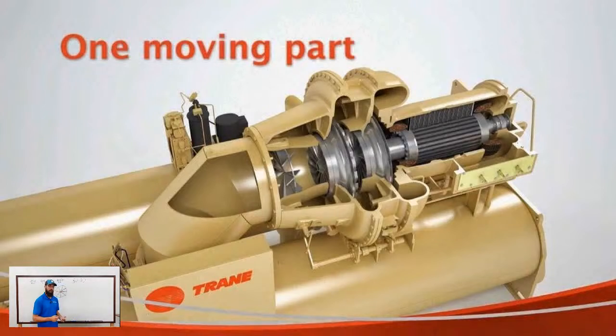What is really critical is that the tolerances between each blade are extremely minimal. To give you an example, York spec is if you can take a dollar bill, fold it over on itself 4 times, roll something across it to flatten it nice and perfectly creased, and then you can fit that little creased dollar bill in between the blades when they're fully closed, it is very likely that chiller is not going to turn on. I'll explain why in a minute. But that is how tight the tolerances are.